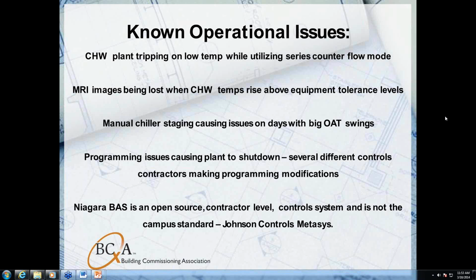So we're either false loading the chiller or we're waiting for alarms and trying to race back and get another chiller going. There were also some programming issues involved. This plant was not commissioned when it was installed in 2008. So there really wasn't any quality control on the original programming, and they also had their control service provider come in and try to fix the programming, to no success on that either. So they're kind of in a pickle there with the chilled water plant. Another issue for them was that they're using a Tridium-based Niagara BAS, which is an open source, contractor-level control system, while the remainder of the campus is using Johnson Controls Metasys as their front-end software.